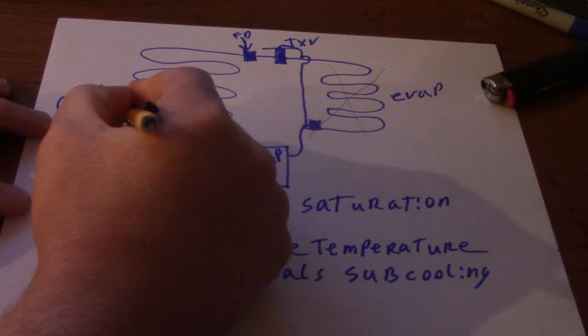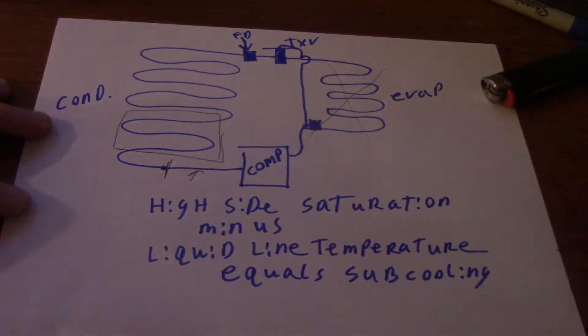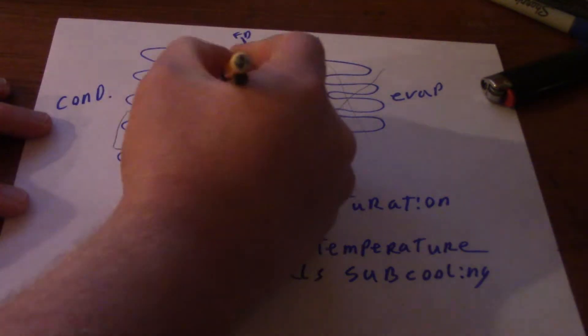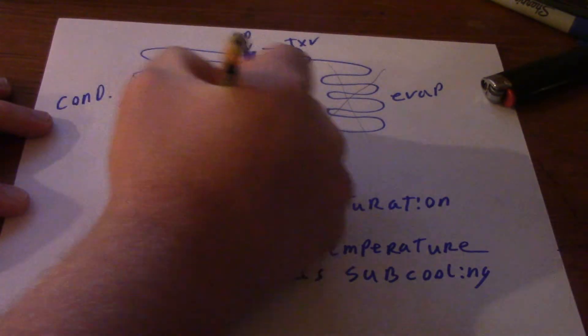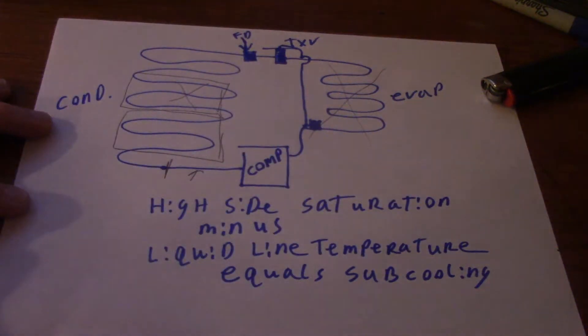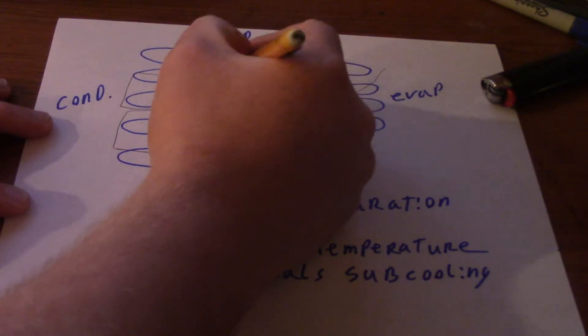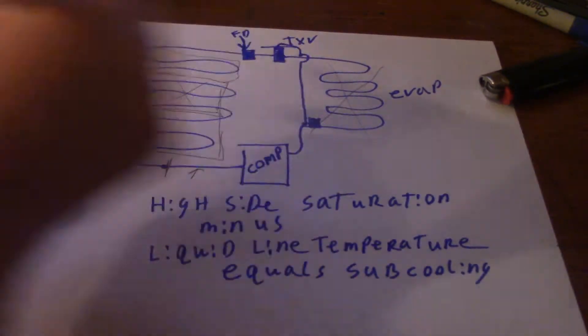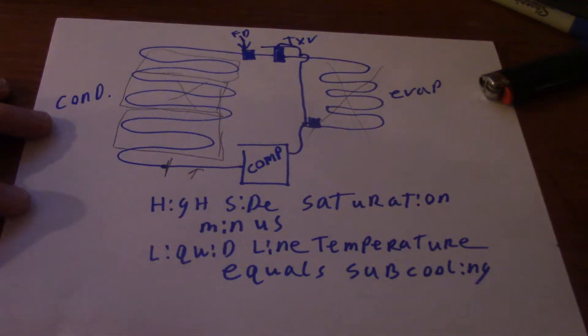Your condenser, right in this area is going to do something we call de-superheating. In this area of the condenser right here is where it's condensing going through a change of state. This last little bit right here for the condenser, that's your subcooling circuit where we're giving additional cooling to the refrigerant.